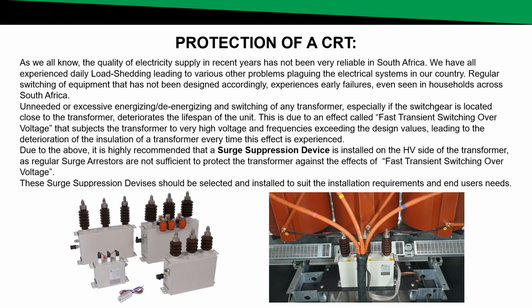Due to the above, it is highly recommended that a surge suppression device is installed on the HV side of the transformer, as regular surge arresters are not sufficient to protect the transformer against the effects of fast transient switching overvoltages. Again, surge suppression devices should be selected and installed to suit the installation requirements and the end user's needs.